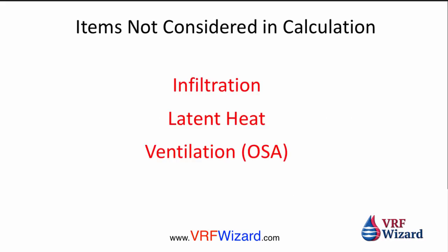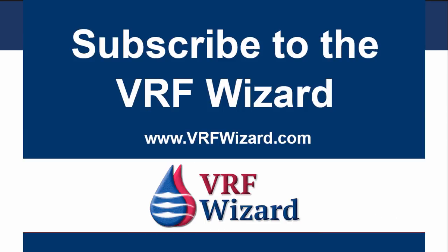Two things we did not consider: infiltration — air that sneaks in from outdoors — which is a very small number, larger in older buildings; and latent heat. People give off latent heat, and outside air ventilation is required for occupant health — we didn't consider that here. The coil will take care of the latent heat; the CFM handles the sensible heat. Please click and subscribe and look forward to our next video.